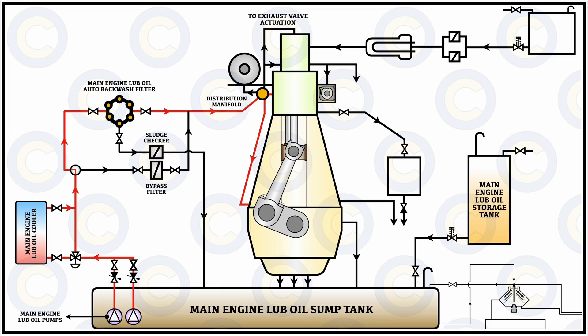After lubricating the crosshead bearing, some part of the oil will also move towards the downside — that is the bottom end bearing or crank pin bearing. The drilled passage in the con rod will allow the oil to pass towards the lower side and thereby lubricate the bottom end bearing. For the main bearing, the line passing from the common manifold will be completely different, because the quantity, flow, and pressure required for the lubrication of the main bearing is very important.